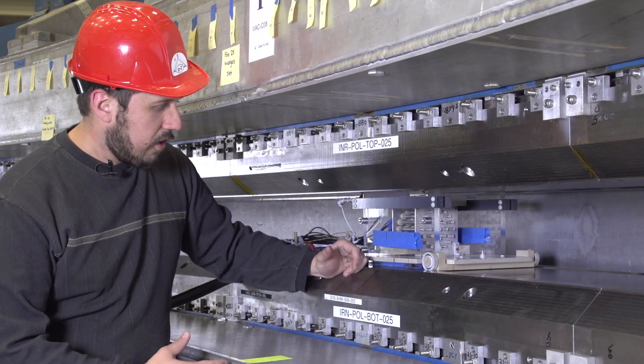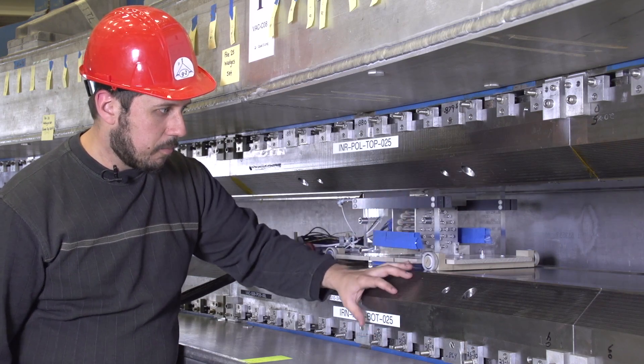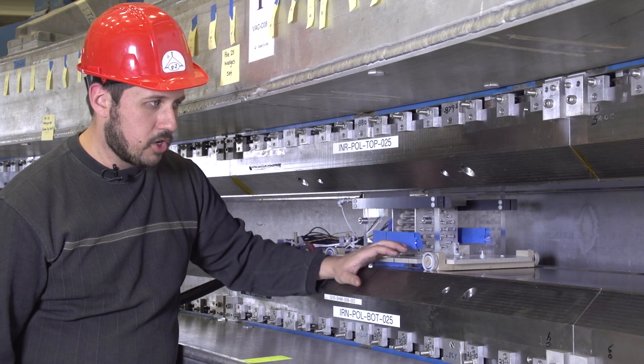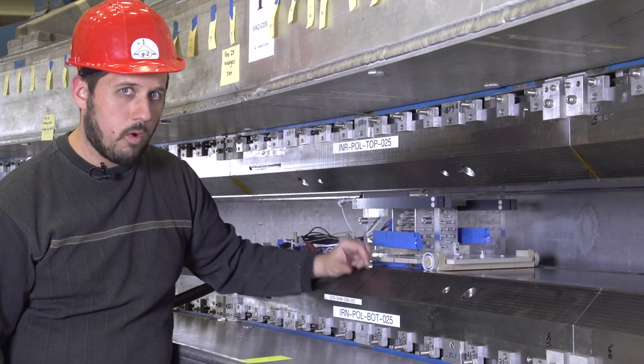The shimming process really has two steps. There's the mechanical adjustment to the pole pieces I just described, but in order to know what to do there, we have to make a measurement. Ultimately the magnetic field is the thing that decides what we need to do.